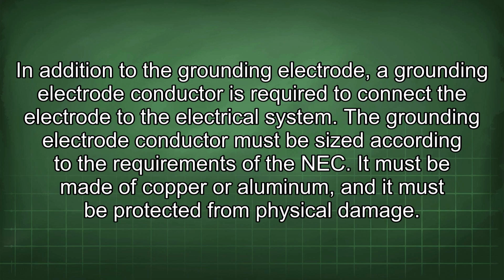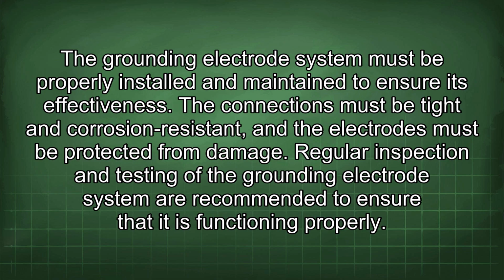In addition to the grounding electrode, a grounding electrode conductor is required to connect the electrode to the electrical system. The grounding electrode conductor must be sized according to the requirements of the NEC. It must be made of copper or aluminum, and it must be protected from physical damage. The grounding electrode system must be properly installed and maintained to ensure its effectiveness. The connections must be tight and corrosion resistant, and the electrodes must be protected from damage. Regular inspection and testing of the grounding electrode system are recommended to ensure that it is functioning properly.